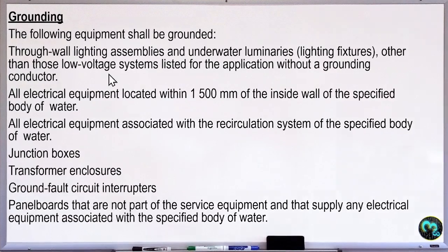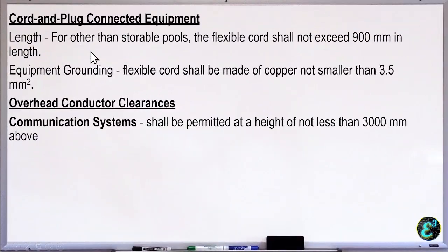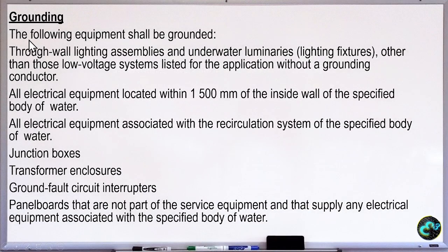So grounding. So the following shall be grounded: through wall lighting assemblies and underwater luminaire fixtures, other than those low voltage systems listed for the application without a grounding conductor. So in general, everything should be grounded unless they are listed, or proven that the equipment itself does not need grounding.